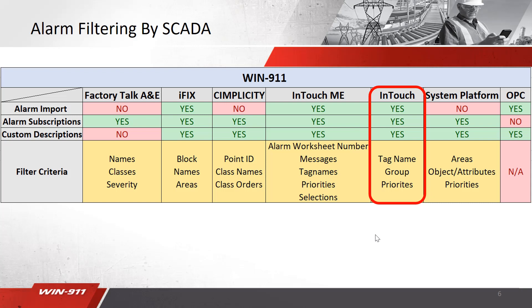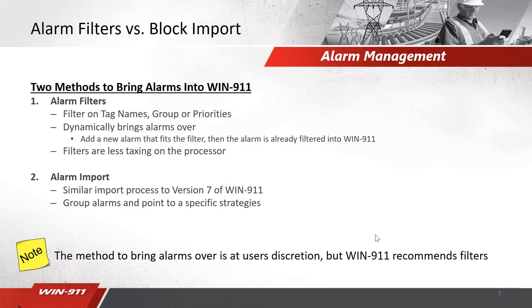If you use subscriptions, you can filter on tag name, group, and priorities. Alarm filters let you filter on those three items and it's a dynamic means of bringing your alarms over. For example, if you have five drive faults and you add a sixth, and you're filtering on the word 'drive' for your tag name, the new item would automatically be included in the subscription with no additional configuration needed. It's a very powerful tool. Filters are also less taxing on the processor and don't take up as much RAM, which is a nice advantage.